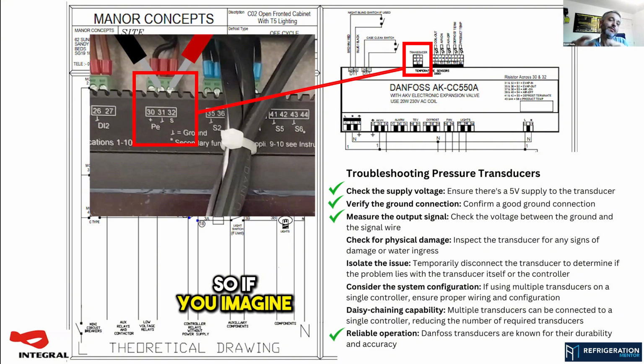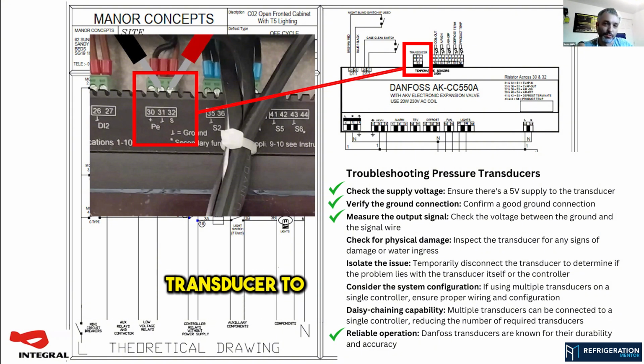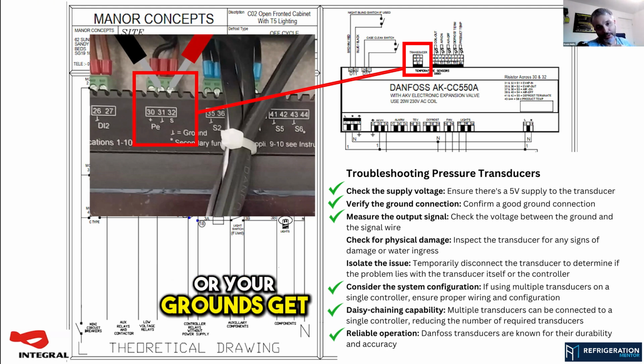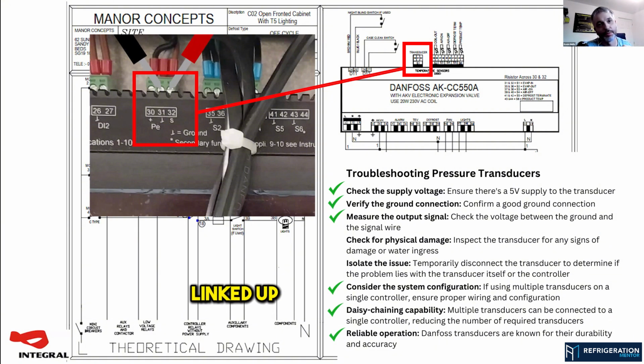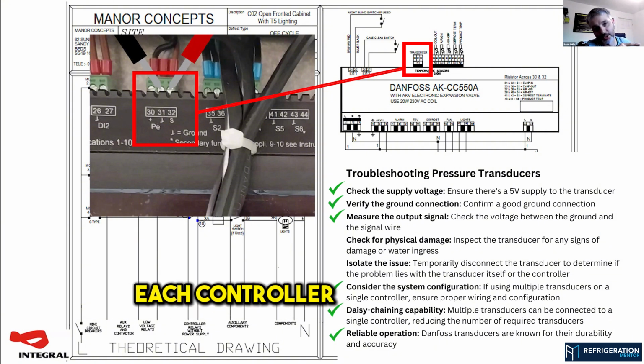Now, Danfoss is very good with transducers. So if you imagine you can use one transducer to run a whole island of cabinets, that's great. Saves you a lot of transducers. You don't need 6 transducers if you've got 6 cabinets on an island. The pressure is going to be close enough, especially on CO2 on all those cases. And Danfoss lets you daisy chain all of that together. So all your 5 volts get linked up, or your grounds get linked up, or your signals get linked up, and you will get the same reading on each controller.